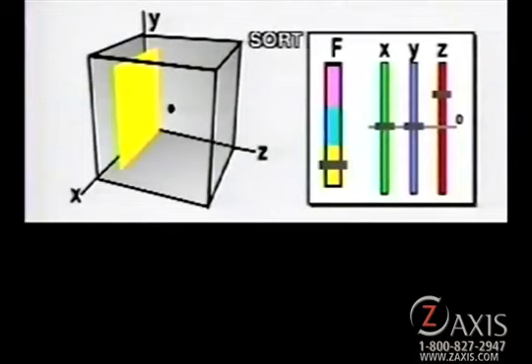In this example, the Z coil is energized and a low or yellow radio frequency pulse is applied. In this condition, the image plane being scanned is indicated by the yellow square inside the scanning volume. Changing to the medium or cyan frequency moves the image plane to the center of the scanning volume, and changing to the high or magenta frequency moves the image plane to the right end of the scanning volume.